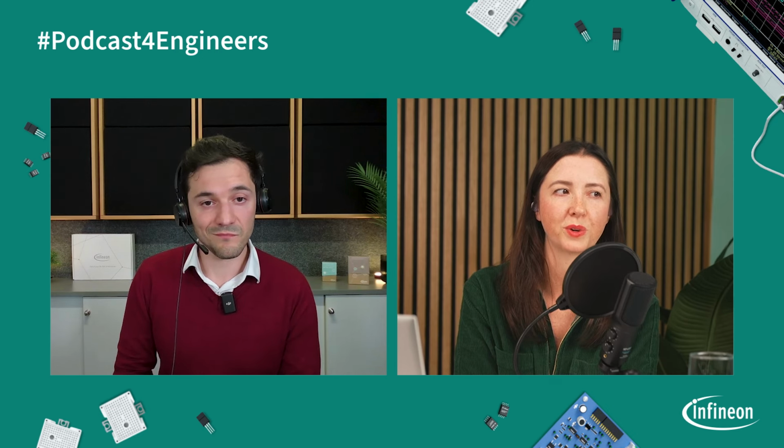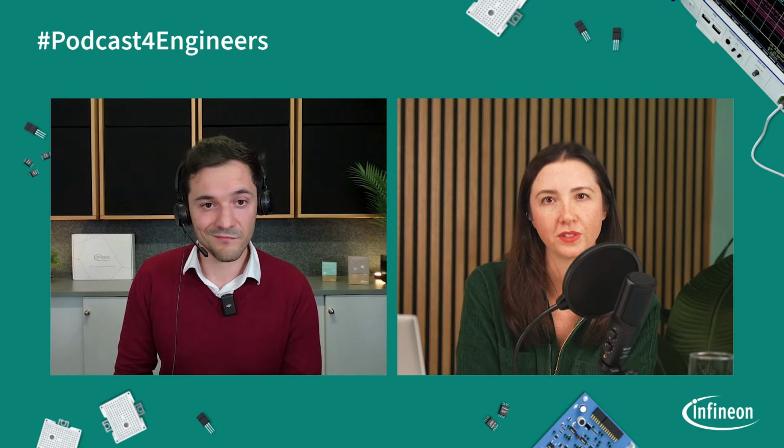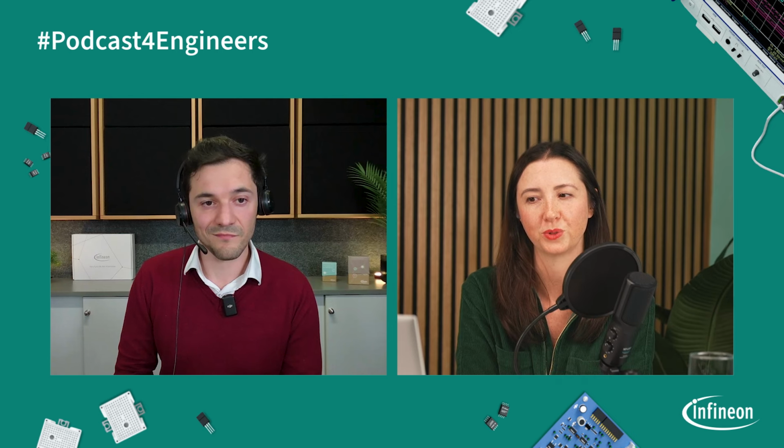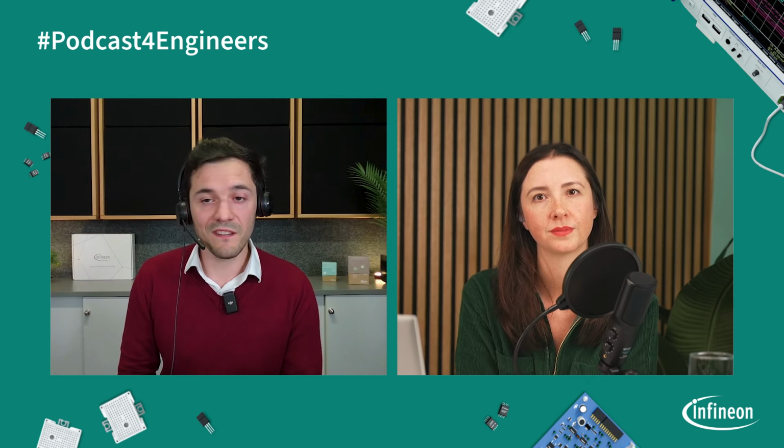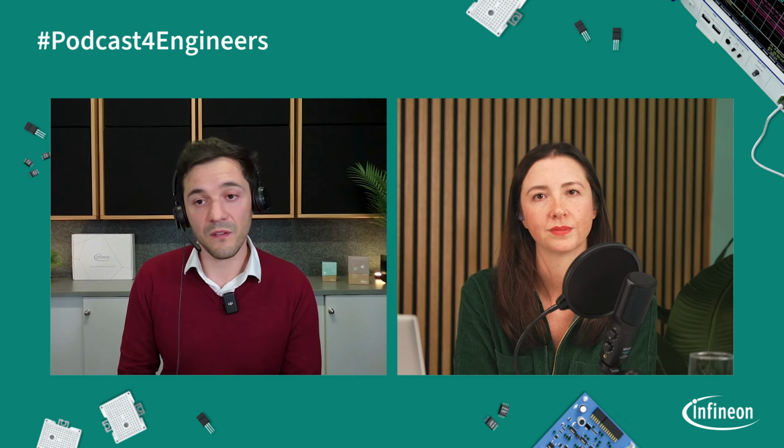Okay, you mentioned the word cost. So total cost of ownership for these two options, what does that look like? Definitely the first option is the efficient one, because you are lowering the high current path. Think about it, you need to cover a long distance on this data center board with a 12-volt rail. Clearly, you have 4 times the losses in those rails compared with the 48-volt solution. That is pretty much clear.